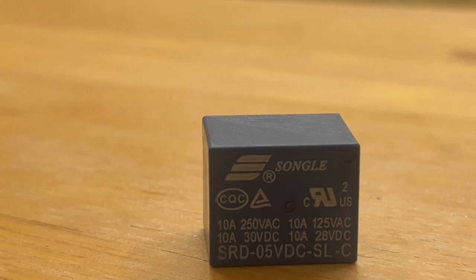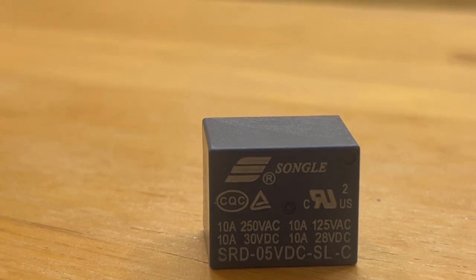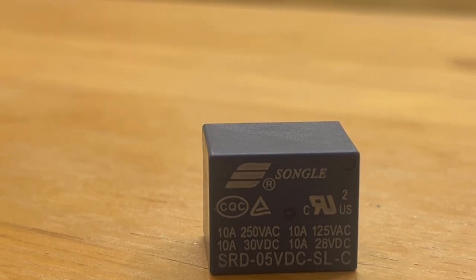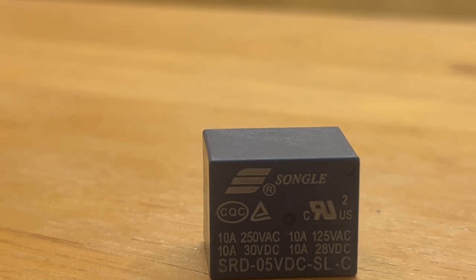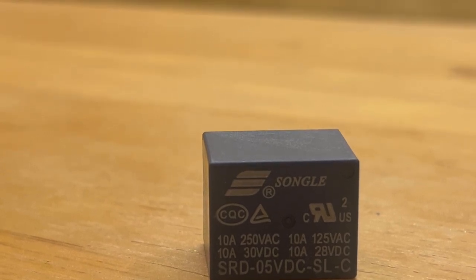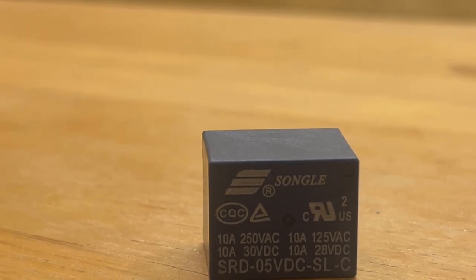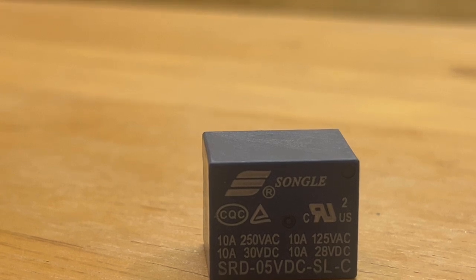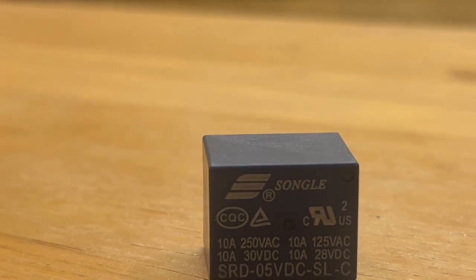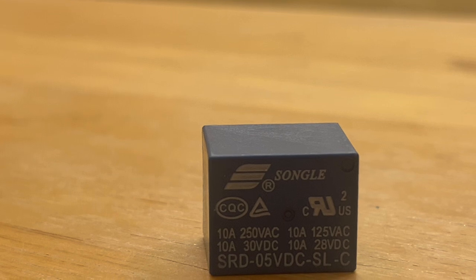So what are some troubleshooting tactics we can use? If the relay clicks but the device is off, it's wrong wiring on the terminals. If the relay doesn't click, there's not enough current to activate the coil. If the relay stays on or off, it's a faulty relay module or a code error.